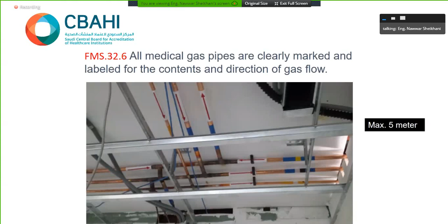We talked at the start of the presentation about an accident because of cross connection. This is what happened: the technician above the false ceiling could not recognize the oxygen pipe, and consequently he installed a new pipe with a different or wrong type of gas. So that's why 5 meters, you have enough distance to recognize the type of gas.